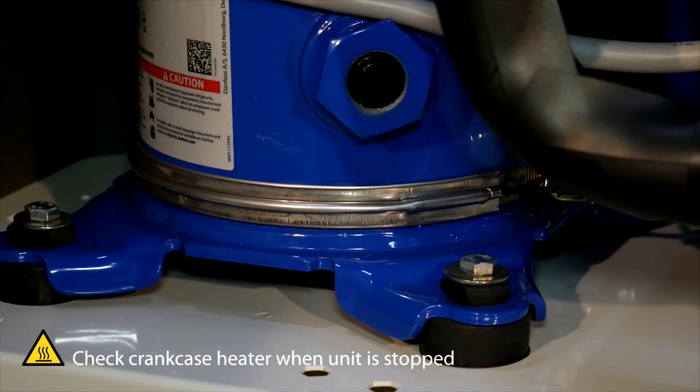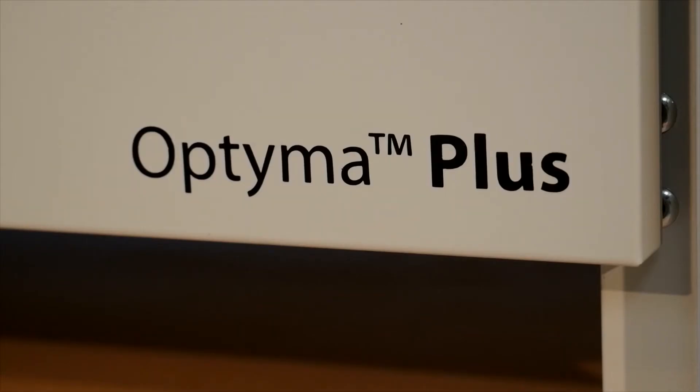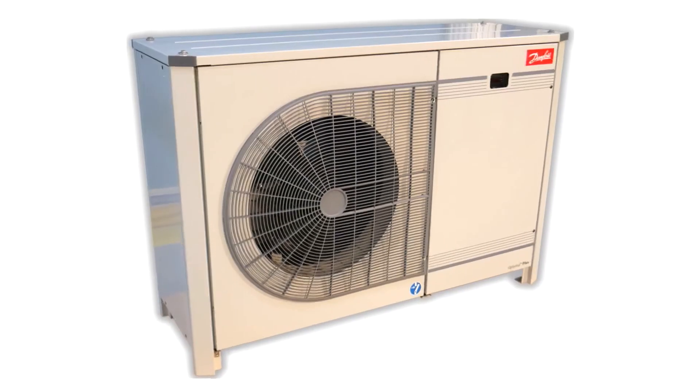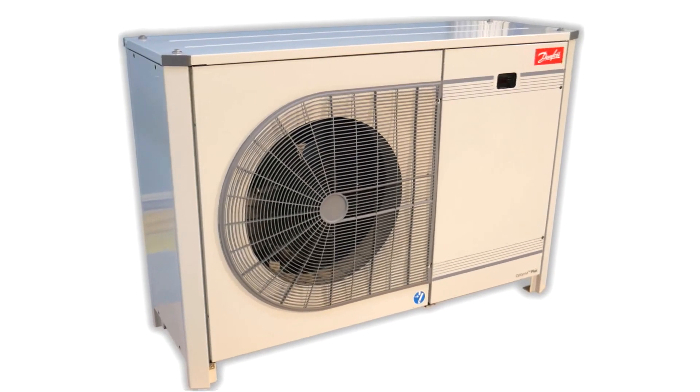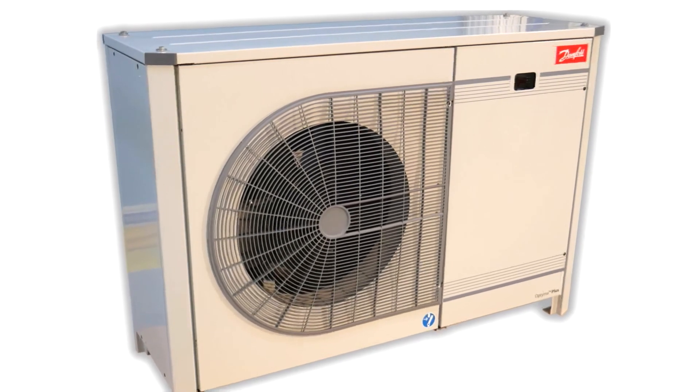Remember, this is a temporary solution and we strongly recommend to quickly replace the controller. The condensing unit cannot permanently work with this configuration as the unit runs at very low pressure and the compressor can be damaged.